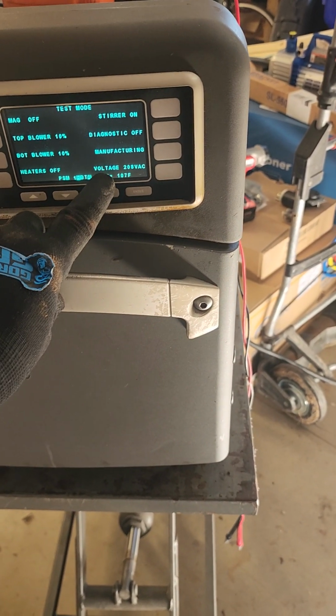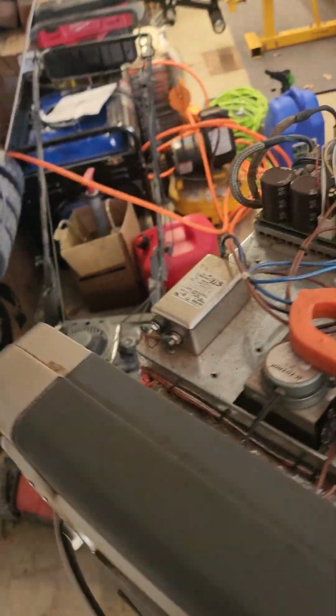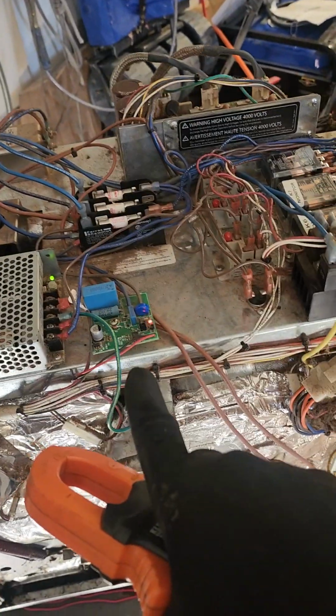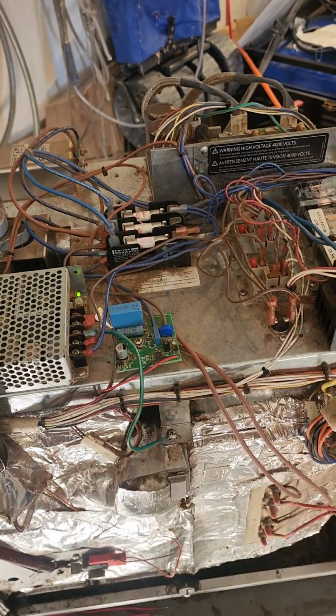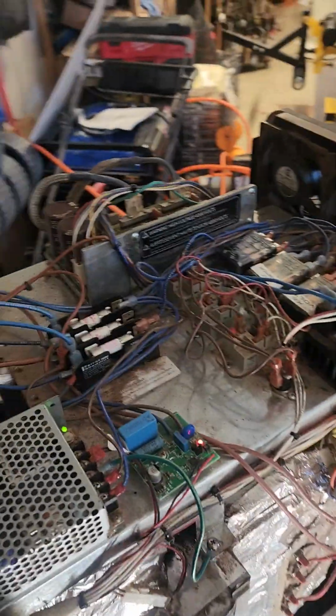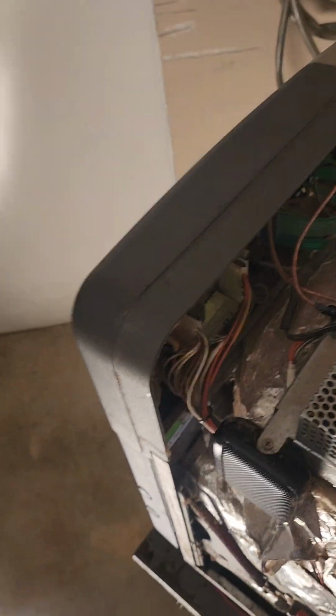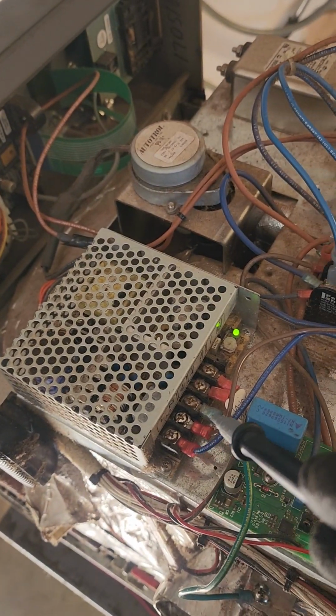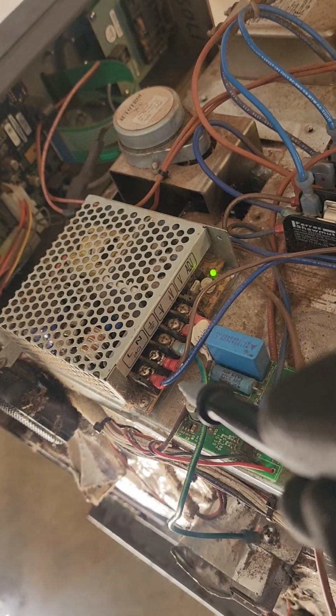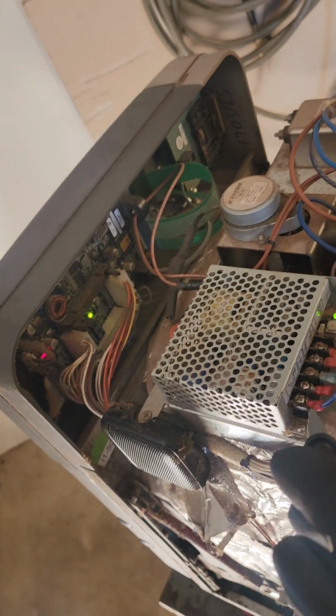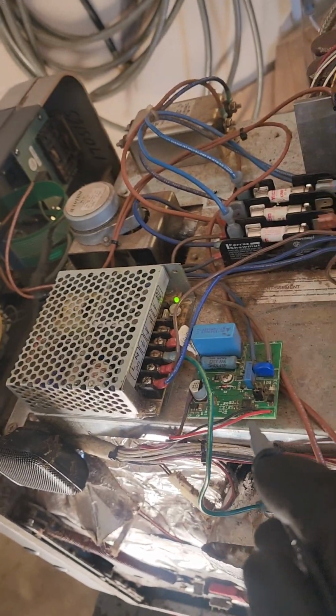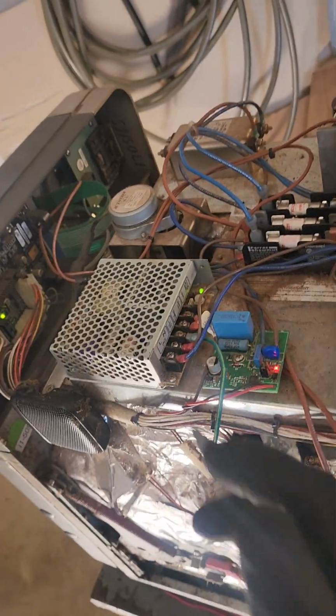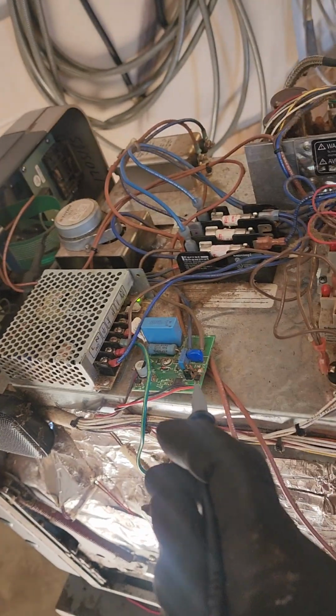So this says 208. It has a voltage sensing module, which is here, that is supposed to detect what the voltage is when you plug it in. So test your voltage. Easiest place for me, I think, the test would be between these two leads right here on the power supply, line and neutral. You should have close to 208 here if the voltage module was reading 208. If you're closer to 240, something's wrong. The voltage module is bad. It's either 208 or 240.